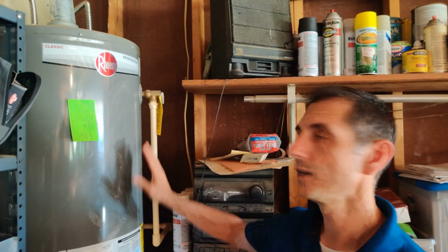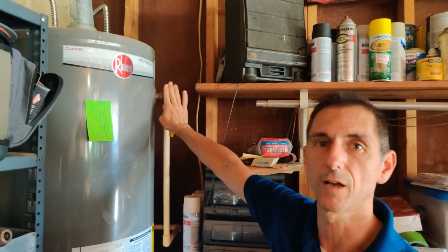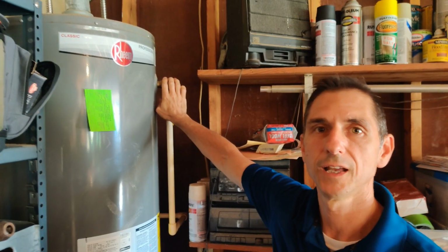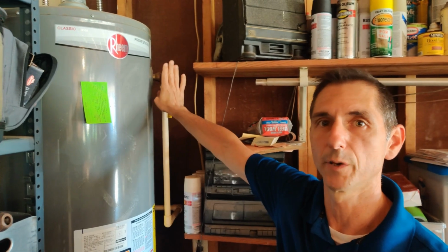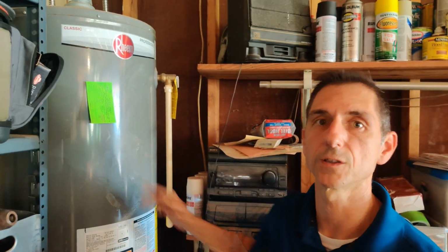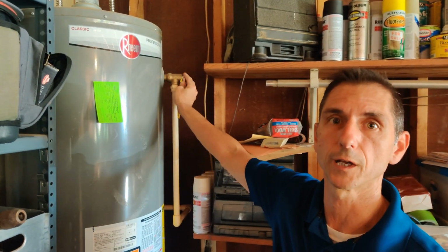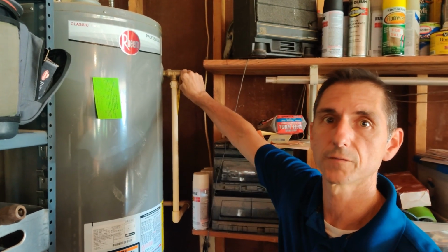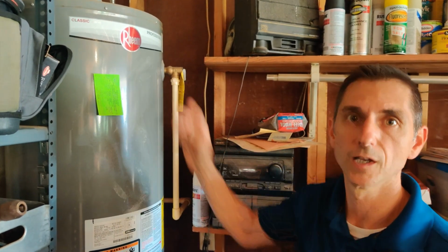One last thing: this valve right here is very important. This is your temperature pressure relief valve, and it should never open. But if it does, it's because your water tank is either overpressurized, overheated, or both. You want to make sure this valve is in good working order, so once or twice a year lift up on this lever and make sure water flows through this tube to the outside of your house. Also, if you're doing any maintenance on a water heater, especially an electric one, make sure the power is turned off. Be safe and cautious about what you're doing.